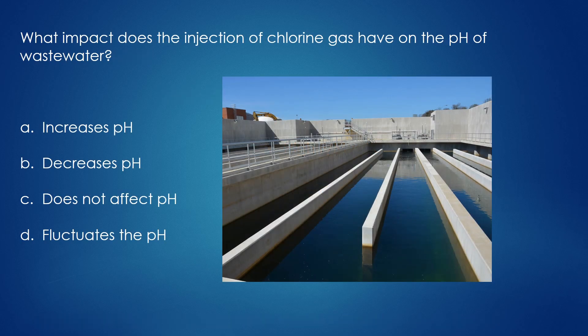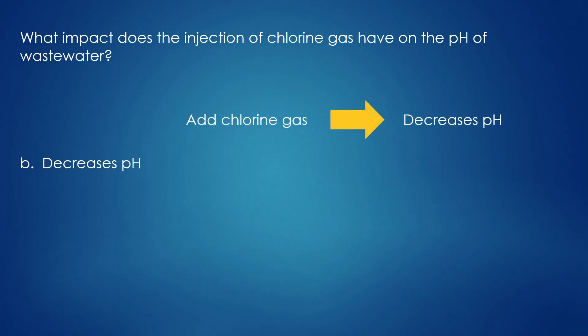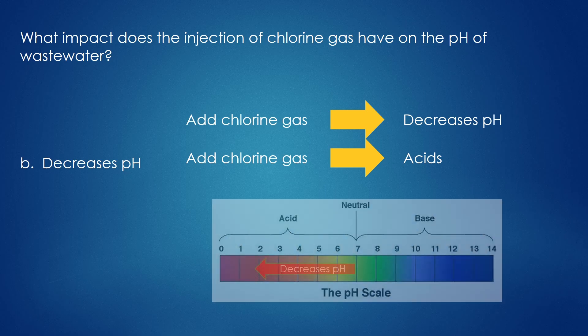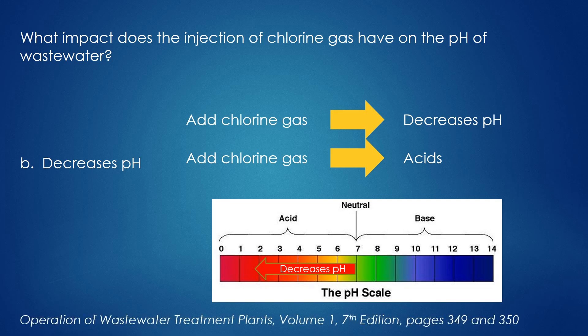What impact does the injection of chlorine gas have on the pH of wastewater? It decreases pH. When chlorine gas is added to wastewater, it decreases the pH. Acids are formed when chlorine gas is injected into the wastewater, and from the pH scale we know that acid has low pH. Therefore, if acids are being formed, the pH must decrease — it moves to the left on the pH scale. So remember, if chlorine gas is added to wastewater, the pH decreases. To learn more, go to the textbook Operation of Wastewater Treatment Plants Volume 1, pages 349 and 350, for more detail.